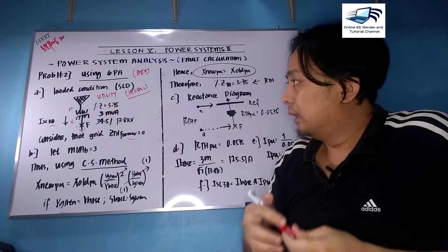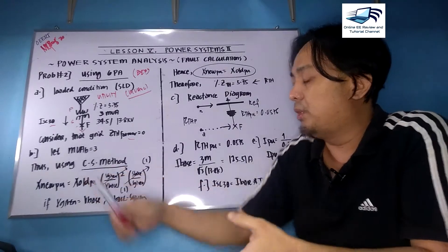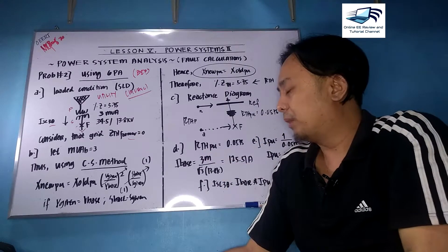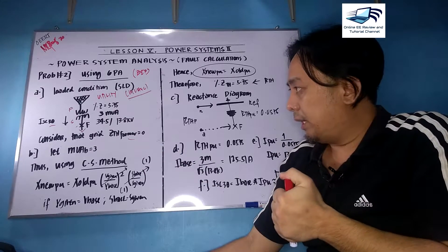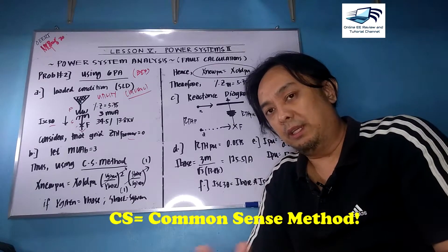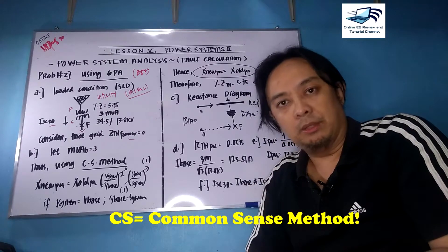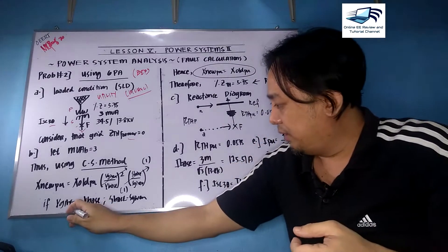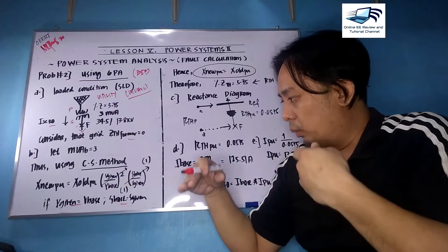Letter B: the second procedure on the six-point algorithm is we need to have a common S base, your favorite number or forever number MVA base. I use three here so we can simplify things. There's a technique I can share with you called the CS method, not Counter-Strike but Common Sense Method. This method is used when your V given equals V base and S base equals S given. When you have V base equal to V given, your pre-fault voltage is simply equal to one.